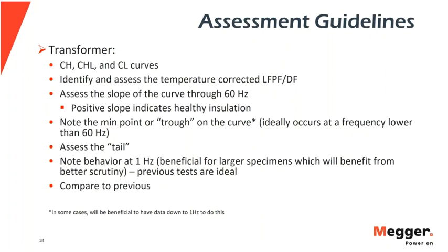Assess that tail, and the expectation is that the tail is going to start to increase with frequency, but we want to keep our eye on how much it increases at these higher frequencies. And I'll give you some visual as the best way to convey what's an acceptable increase in the tail or not. And then if we have the 1 hertz data available to us, we certainly want to note the behavior of the response at 1 hertz.